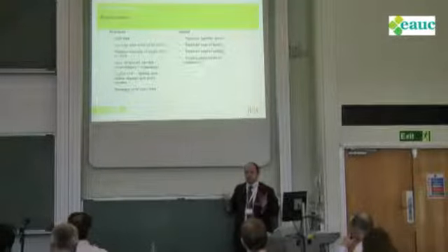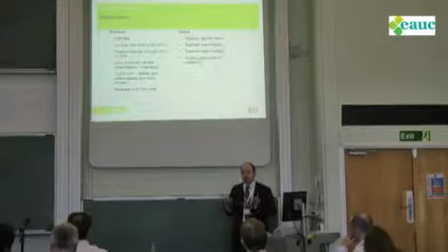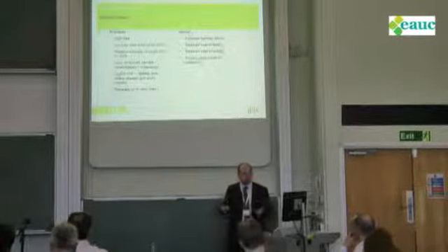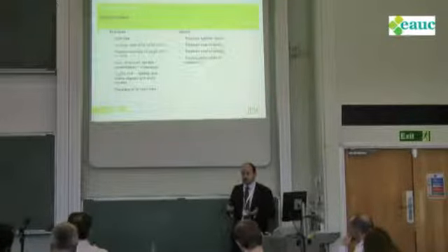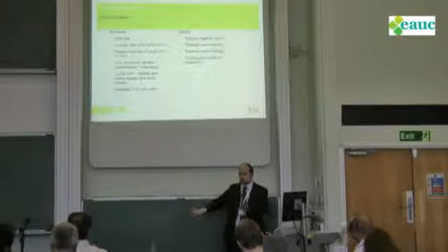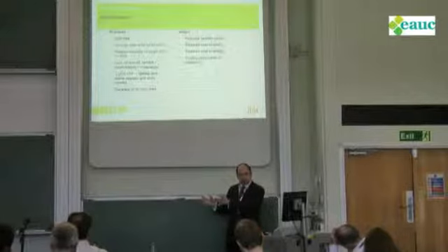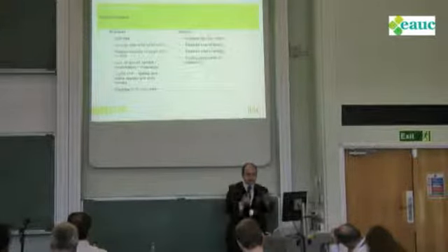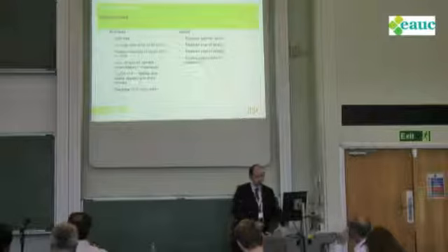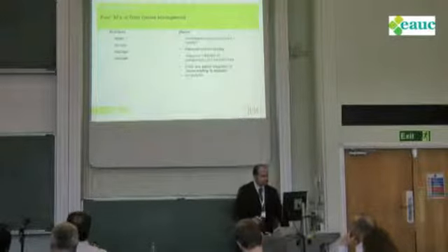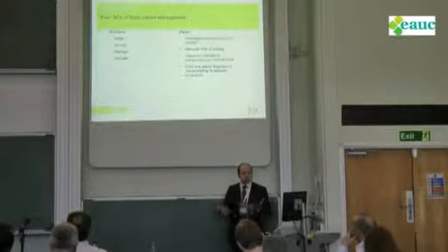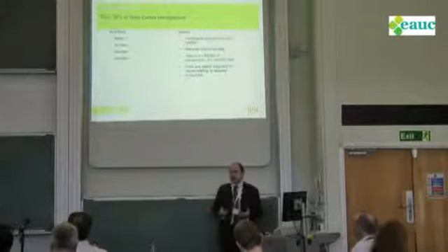If you're going to turn the temperature up in your main data hall, and you've got UPSs in there, it's going to restrict the temperature to which you can turn it up. So if you put them in a separate room, you can keep that environment at one temperature while you turn up the temperature in your main data room. Simple, effective. So those are some of the best practices within your data center.